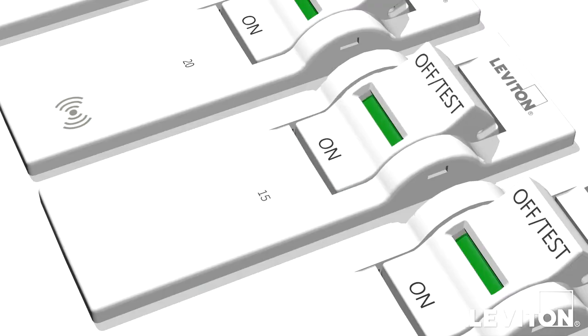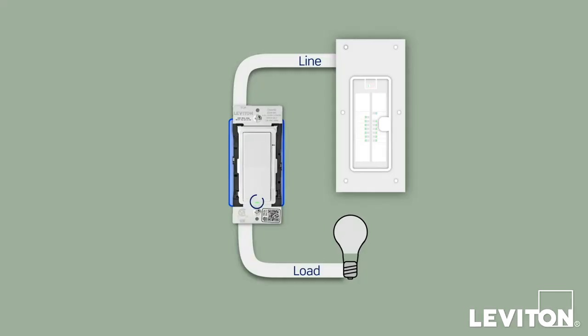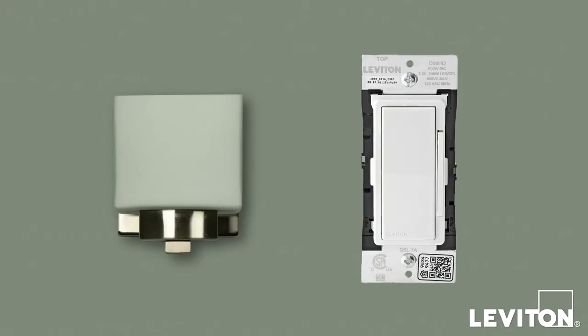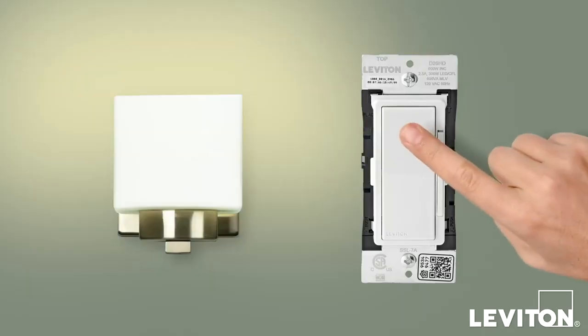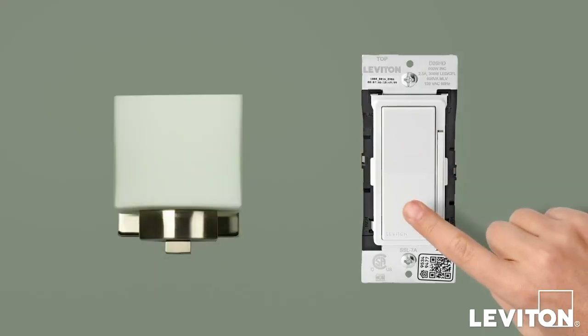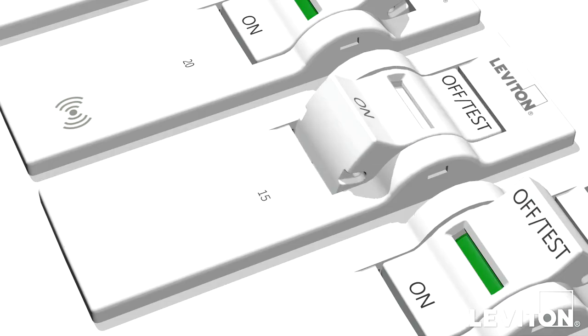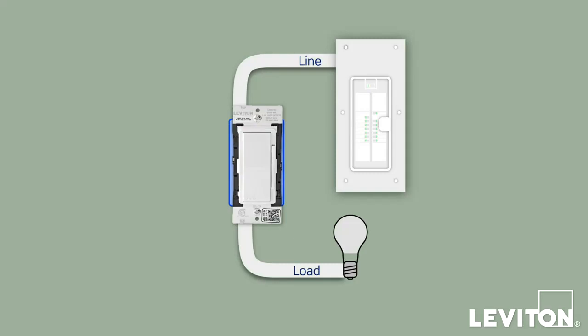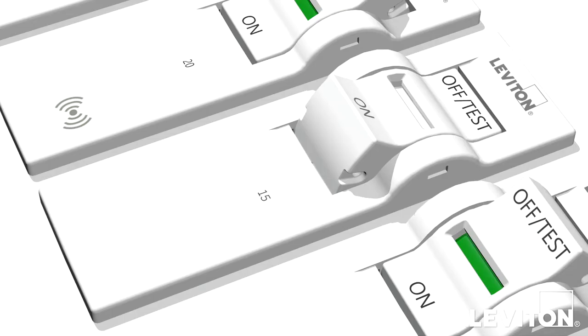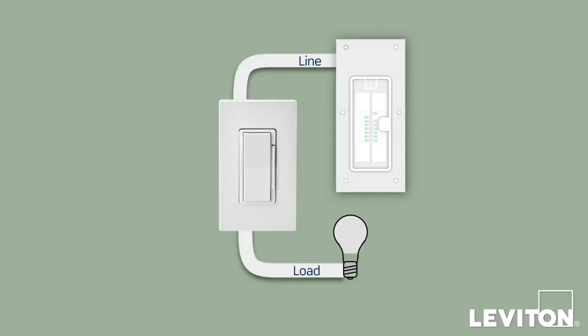Restore power at the circuit breaker and the status light will blink green. Press the top of the switch to turn the light on and the bottom to turn the light off to verify you have properly wired the device. Turn off the circuit breaker to shut power. Complete the installation by tightening the mounting screws into the wall box. Do not over-tighten. Then, install the included screwless wall plate. Restore power at the circuit breaker and the status light will blink green.